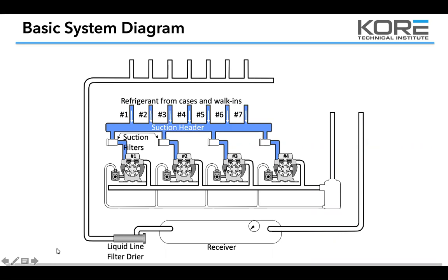We can talk about float strategies another day, but you can get pretty dynamic in how you stage for energy efficiency. All the compressors are tied to the same suction header, so depending on how much heat load is coming in through those lines and raising that suction pressure, transducers on the suction header tell it to bring on stage one. If stage one doesn't bring that suction pressure down to a satisfactory point within a certain amount of time, it ramps stage two, then stage three.